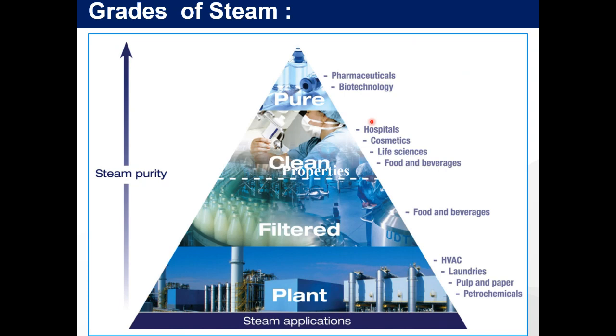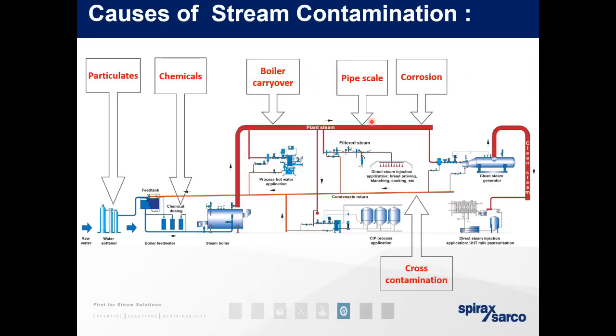Not so far. Okay. So causes of contamination. So particulates coming from your water softener, raw water in. Chemicals that have been added to the water to cleanse it. Boiler carryover. So if your boilers are running inefficiently, you can get carryover of those chemicals and that polluted water into your system. Pipe scale. So from the carryover, from the water residue, you can end up with scale, corrosion.